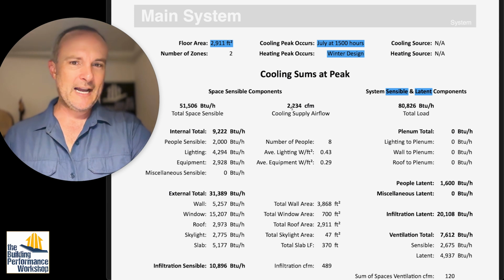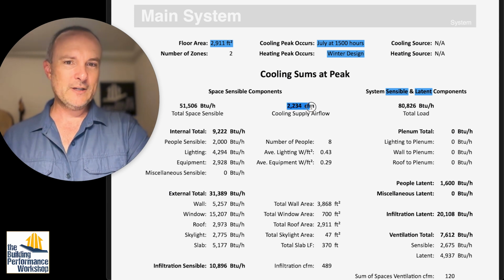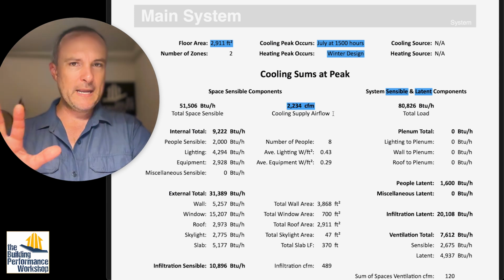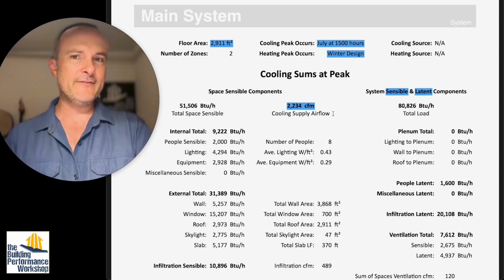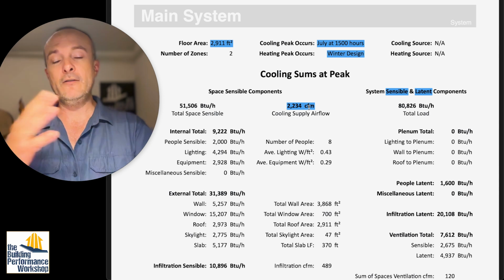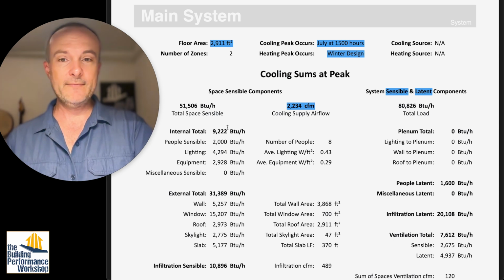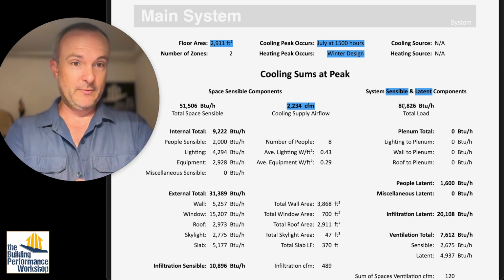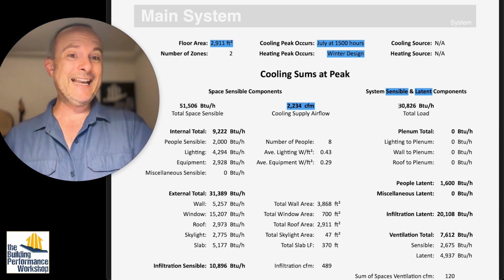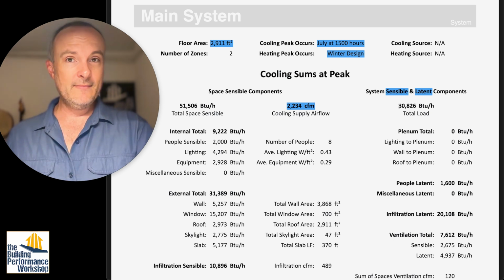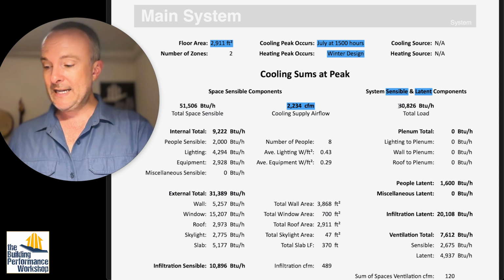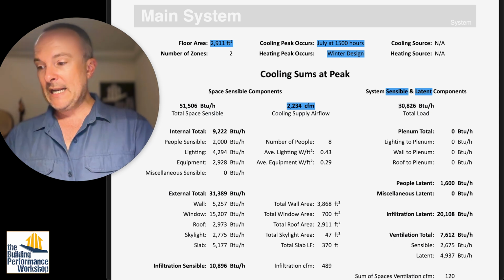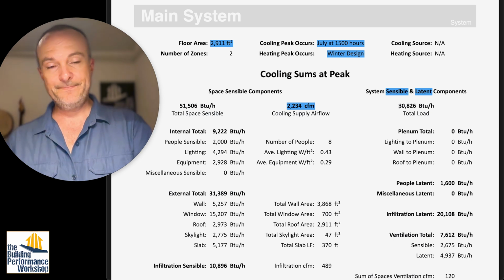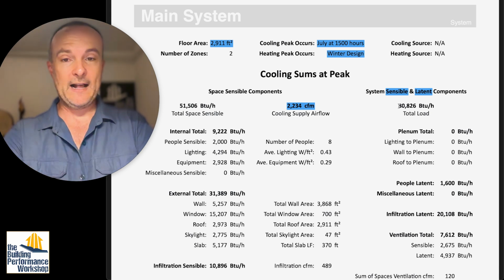The cooling supply airflow is 2234 CFM. That's bigger than a 5-ton. That's about 5.5 tons of cooling flow if you're using a typical 400 CFM per ton, which these guys are clearly not, because we've got a great big load here. At 12,000 BTUs per ton, if we take roughly 80,000 divided by 12,000, that's 6.7 tons that are needed in this calc.